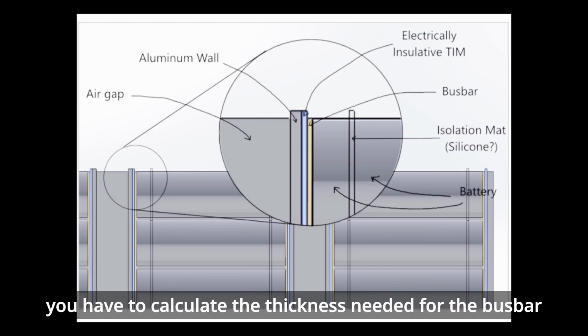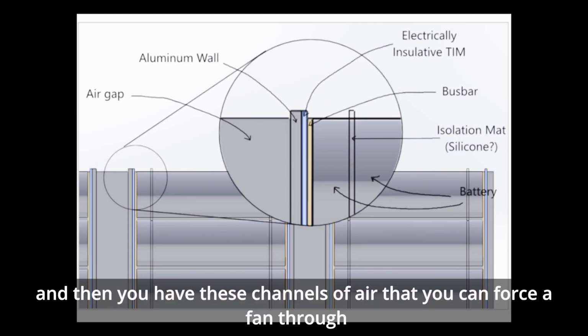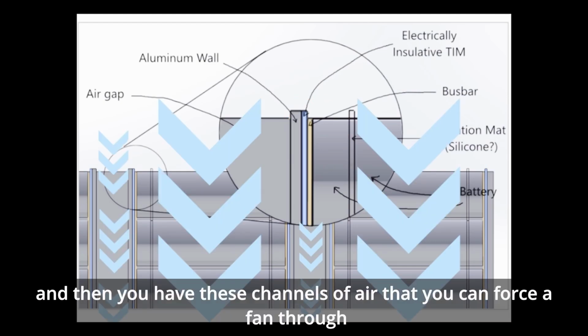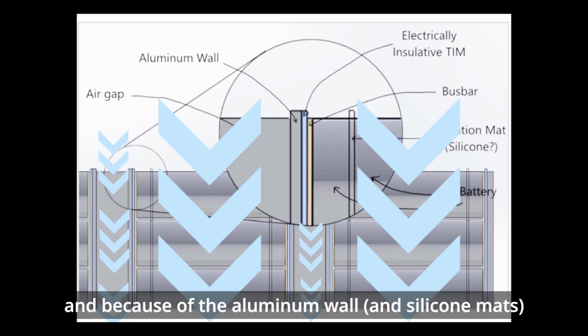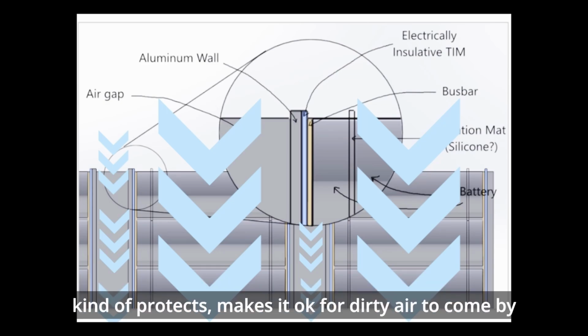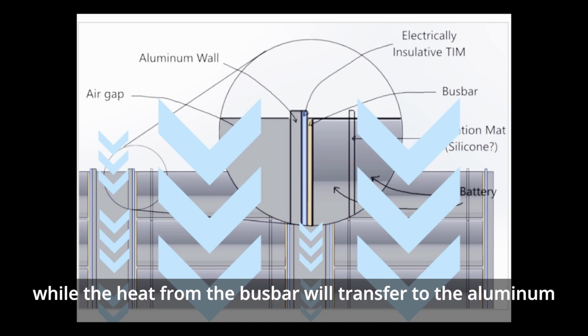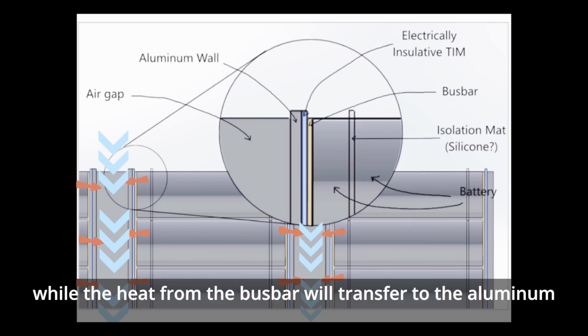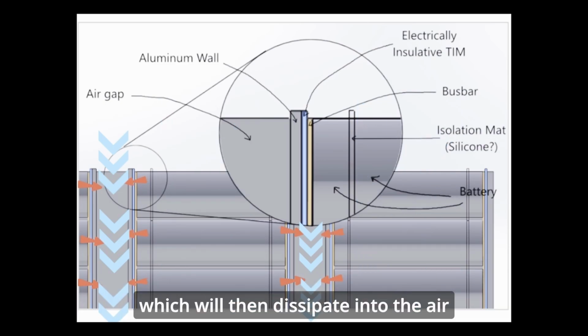You have to calculate the thickness needed of the bus bar, and then you have these channels of air that you could force a fan through, and because of the aluminum wall it's okay for dirty air or whatever to come by, but the heat from the bus bar will transfer to the aluminum, which will then dissipate into the air.